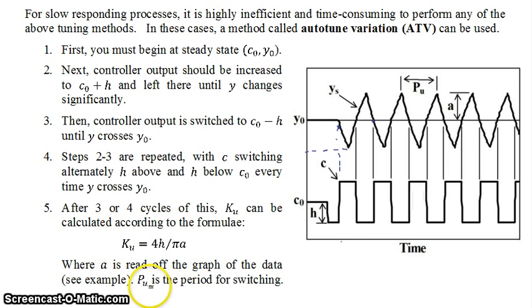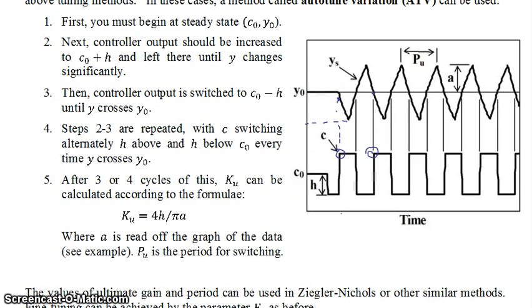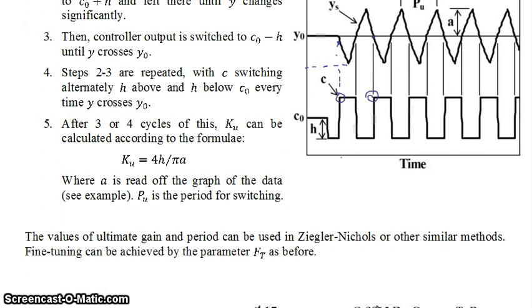And then your ultimate period is how long did it take you to switch. The period for switching would be from this point to the next similar point in the next wavelength. That will give you your ultimate period or ultimate gain. Once you have those, you can use something like Ziegler-Nichols or any other similar method that would use ultimate period or ultimate gain. Once you have your Ziegler-Nichols tuning parameter, you can fine-tune your controller using this parameter F_T as before.